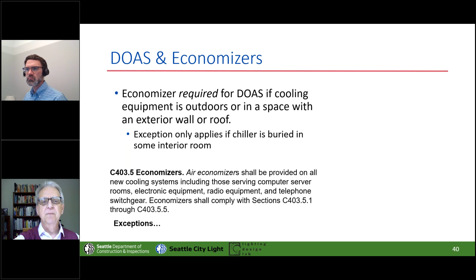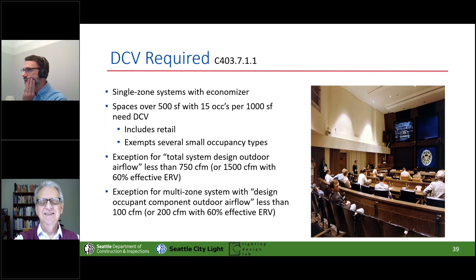Oh, and I got the answer for what would require 100 CFM per person. It's really weird ones, and it's mostly really air exchange based. So it's prison cells, nail salons, barbers. It's things where it's really more about dilution of air than true ventilation. Okay. Where the exhaust rate would drive you up.